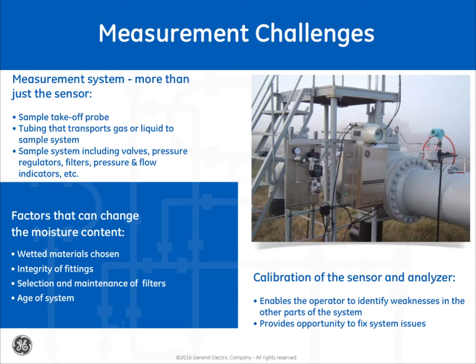Common to all technologies, the sensor is only one component in the moisture measurement system. The measurement system includes the sample system, the tubing that transports the gas or liquid to the sample system, and the sample takeoff probe. Typical sample systems can include valves, pressure regulators, filters, and pressure and flow indicators. The wetted materials chosen, the integrity of the fittings, the selection and maintenance of the filters, and the age of the system all can offer opportunities to change the moisture content of the gas or liquid that reaches the moisture sensor element. Weaknesses in design, implementation, or maintenance may express themselves as calibration issues.